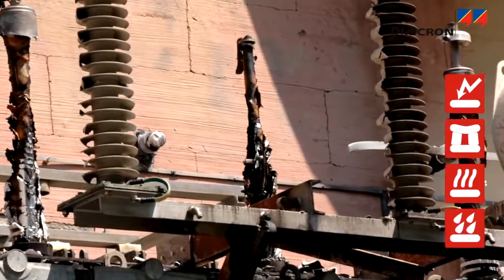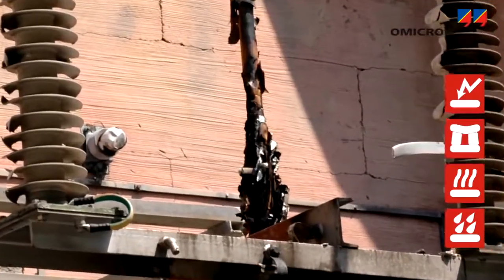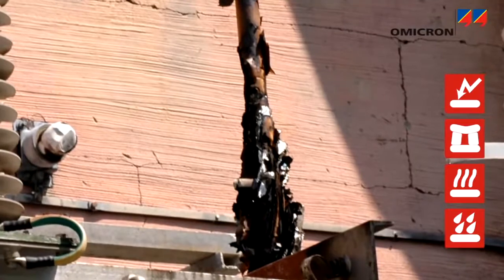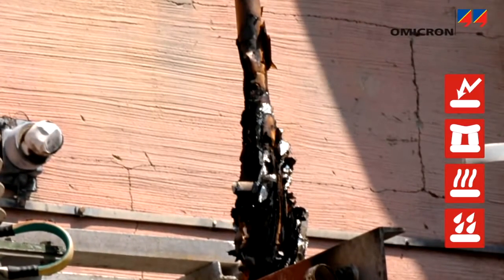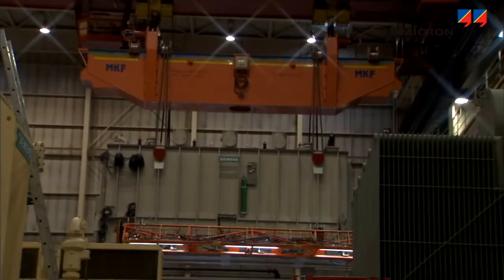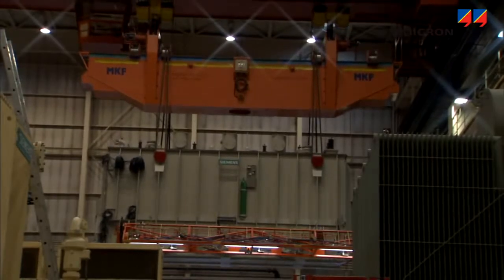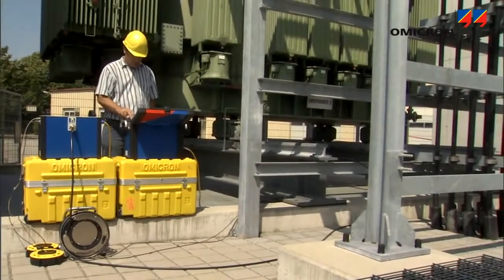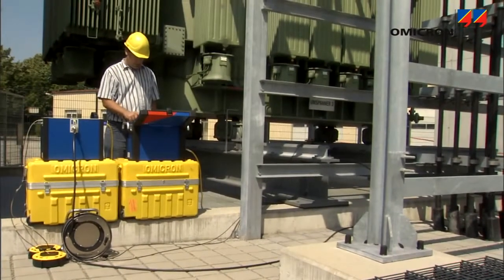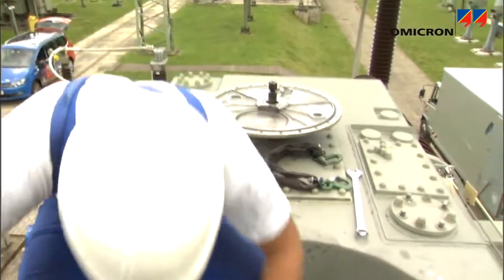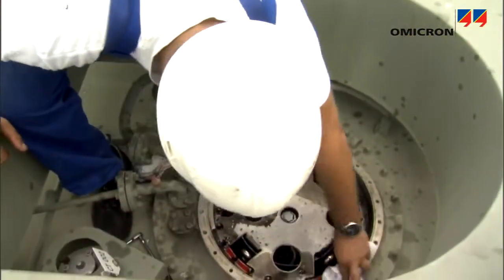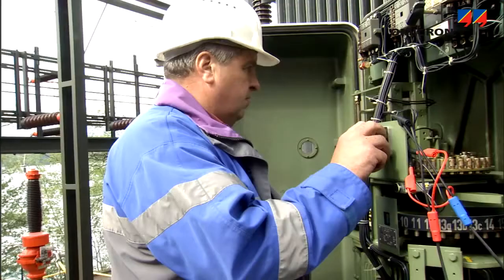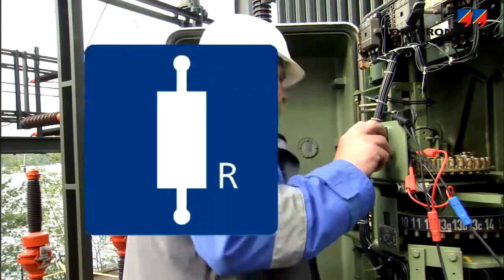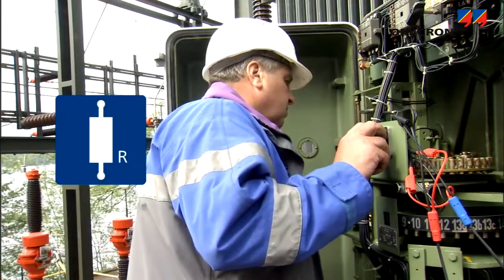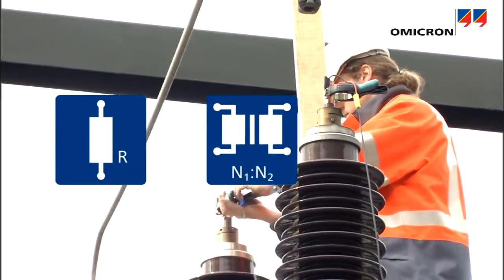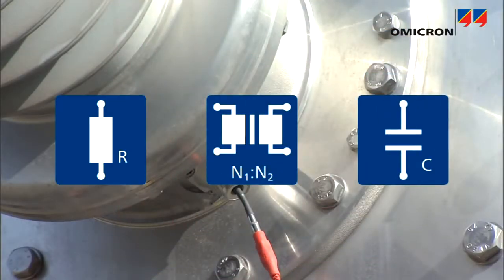Transformer failures caused by these stresses can result in explosions, subsequent fire, and costly aftereffects such as long outages caused by cleanup and plant repair, as well as the long delivery times of new transformers. Therefore, utilities and service providers test power transformers in order to assess their condition, schedule maintenance work, and plan the replacement. The most common electrical methods include measuring winding resistance and checking the tap changer, measuring transformer ratio and excitation current, and capacitance and dissipation factor or power factor measurements.